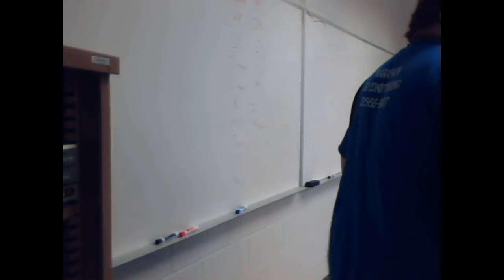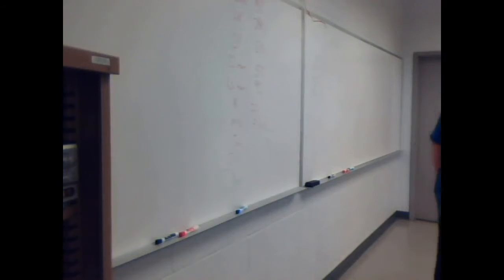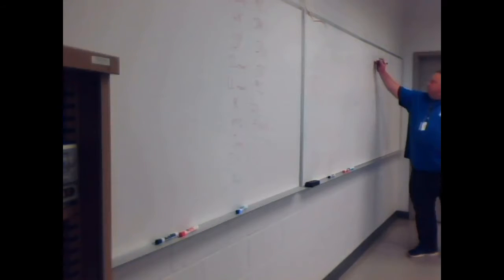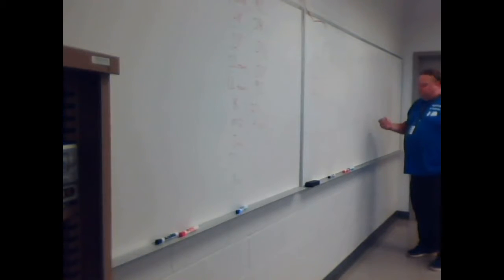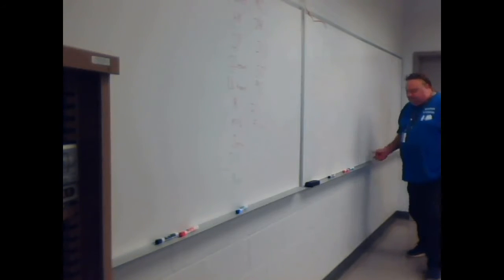So how do I go about figuring out what I should expect from head pressure? Just add 30 to the head. Add 30 to what? Temperature. The ambient temperature where that condenser is. I said it was 95. Plus 30.